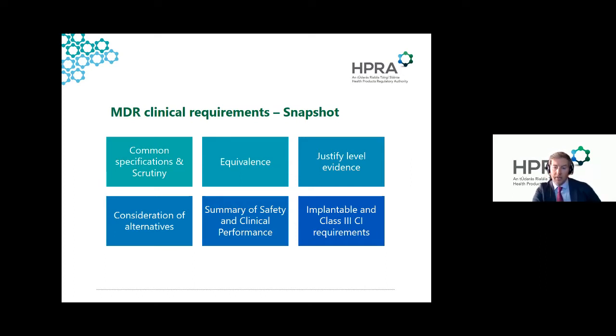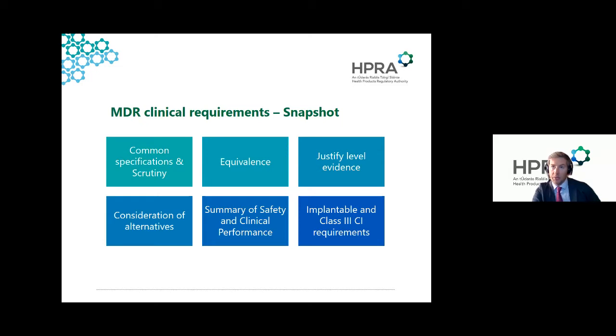In terms of clinical evaluation methodology, MDR has more detail, including aspects such as justifying the level of evidence and considering alternatives. These methodology principles have more detail in the MDCG guidance documents. Transparency is a key goal of MDR — one of the first guidance documents produced by the CIE working group was the Summary of Safety and Clinical Performance, a standard template of information regarding clinical evidence for high-risk devices. Generally, clinical evidence requirements for high-risk products have increased, as have the rules for claiming equivalence for high-risk products.